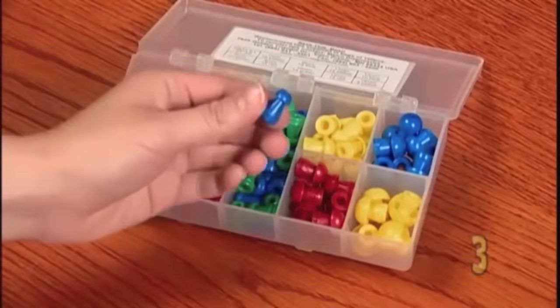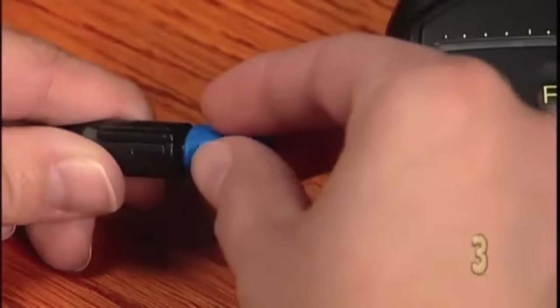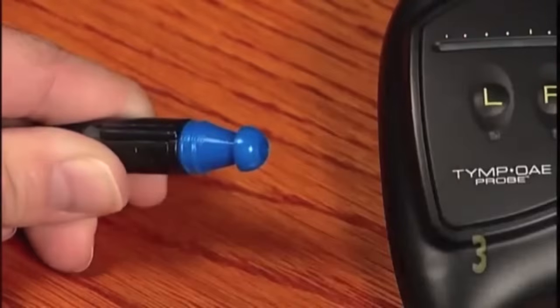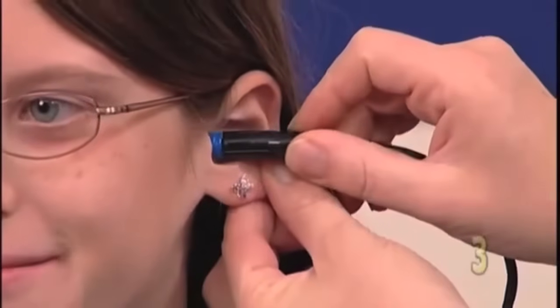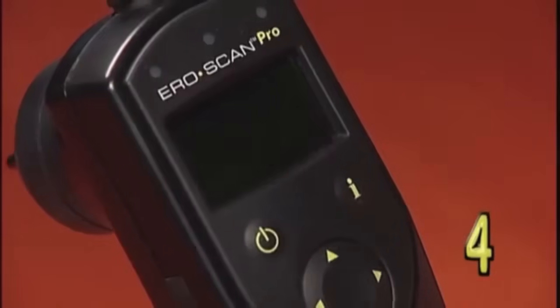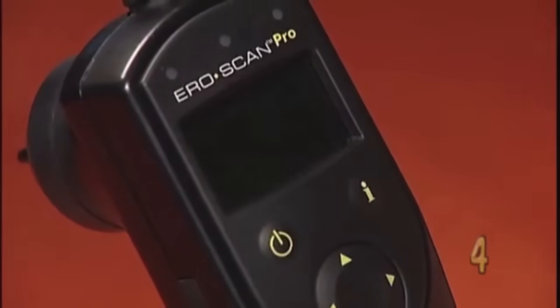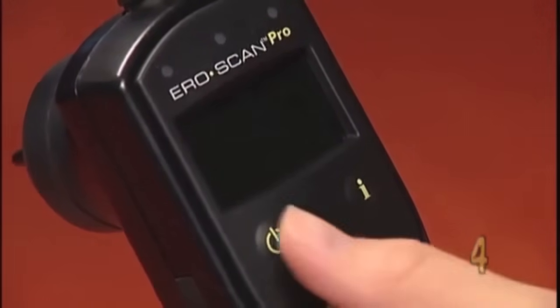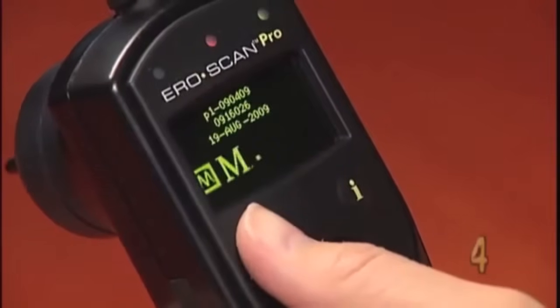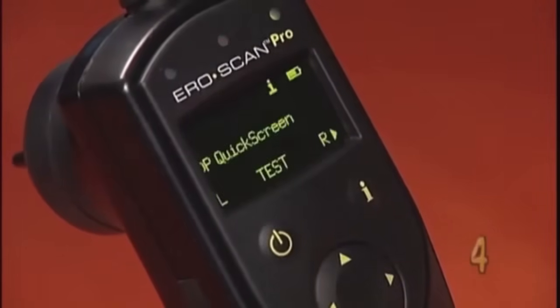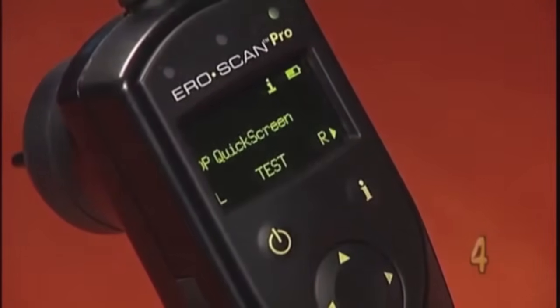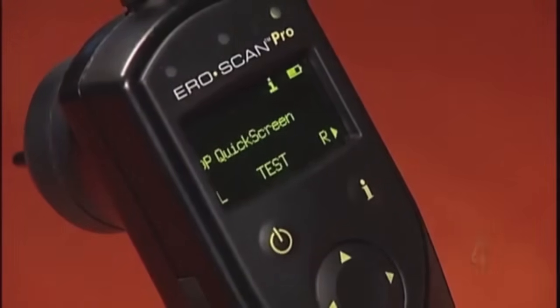Select a disposable ear tip from the kit that was supplied with the system and place it on the probe. The proper ear tip for each patient will be the one that is sized correctly to seal the probe in the ear canal. Power up the unit by momentarily pressing the power button located on the control panel of the Ero Scan Pro unit. When the unit powers up, Quick Screen will be displayed on the menu. This test is a good general screening protocol, and we'll use this test in our example.